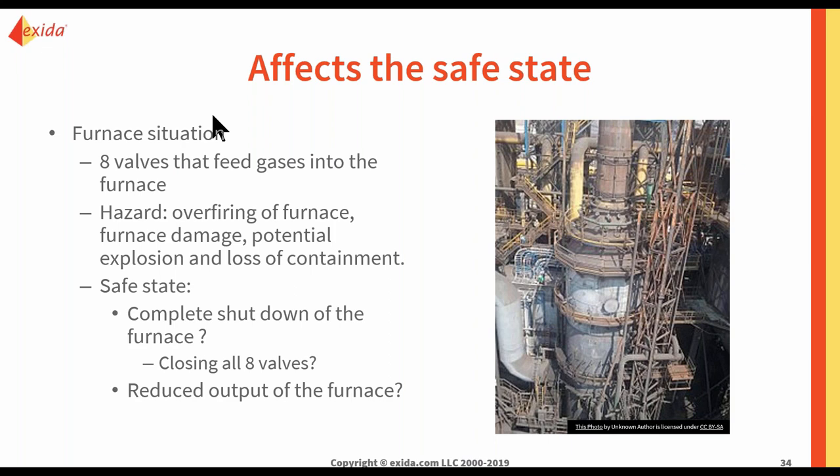Because if we need to shut down the whole furnace, we need to close all 8 valves. Then if you know about SIL verification, closing 8 valves, 8 out of 8, is never going to achieve any kind of SIL for you. And that is a very common problem when I see people talk about overfiring a furnace. Because of the design limit and design integrity, a furnace can sometimes allow that to happen for days or even weeks without creating an explosion or loss of containment. So in that case, we're overestimating the consequence.